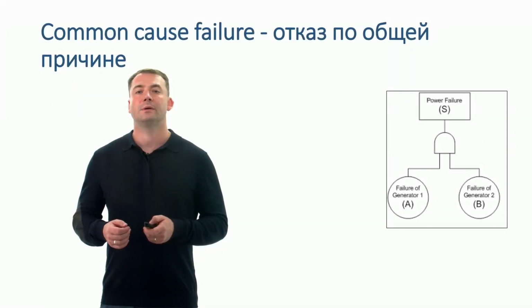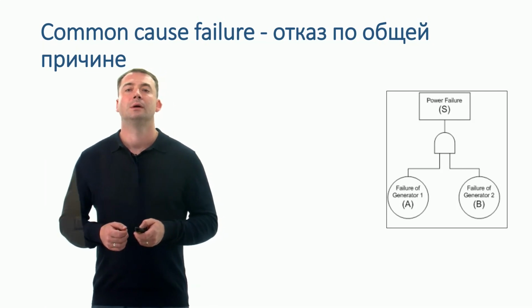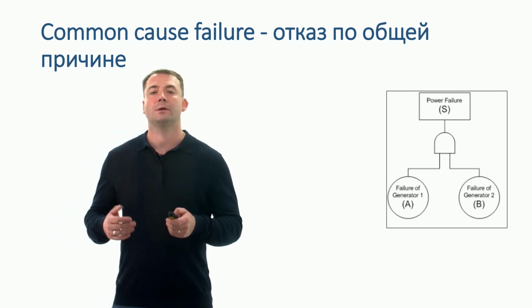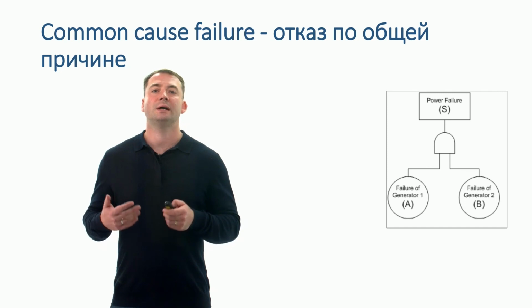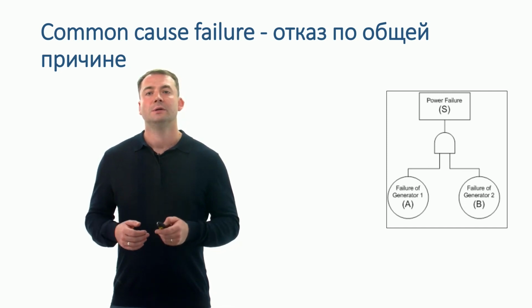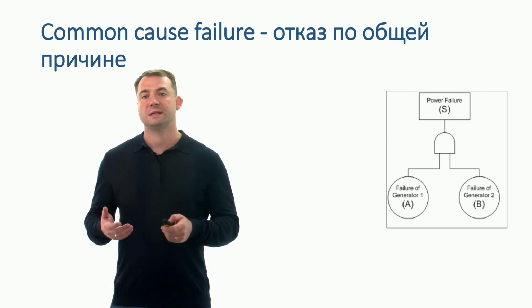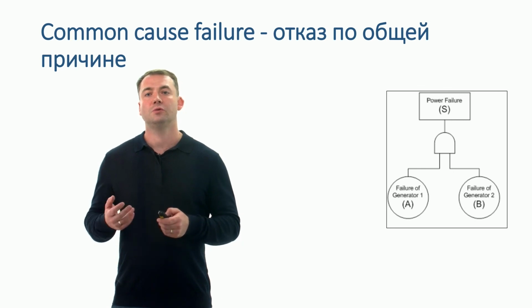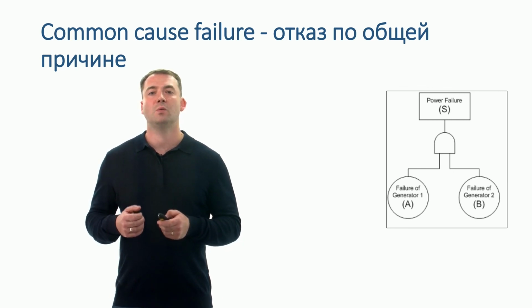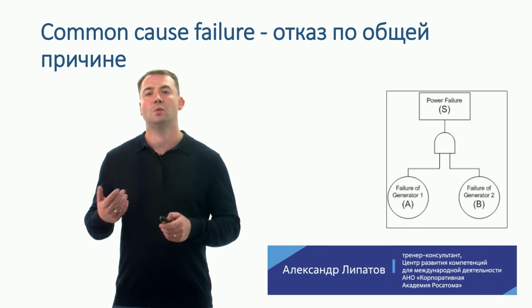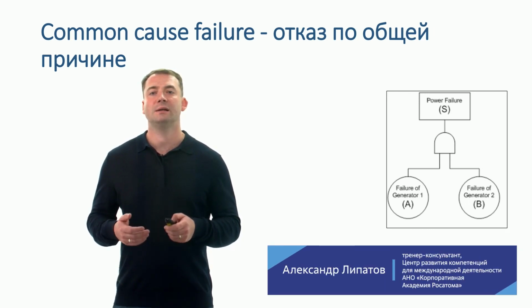Common cause failures occur when multiple, usually identical, components fail due to shared causes. For example, if two generators are maintained by one person who is using an incorrect maintenance procedure, and one generator fails, it is highly likely that the other generator will fail as well.